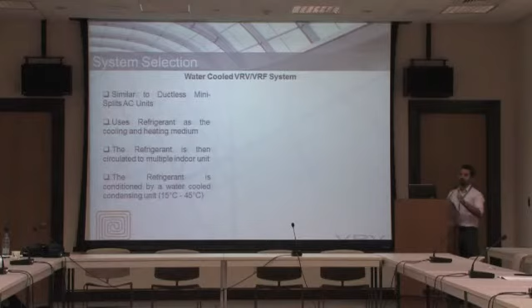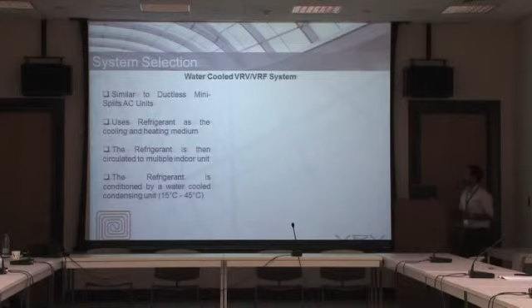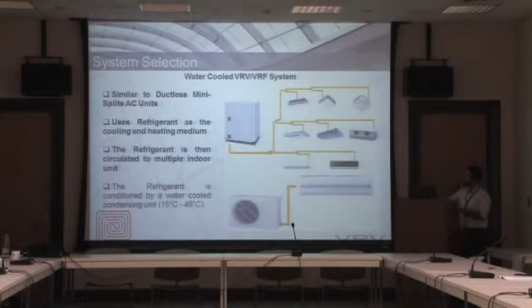Starting with the water-cooled VRV. Honestly, I didn't know what the water-cooled VRV was before I started this project. We usually work with an air-cooled VRV. VRV or VRF stands for variable refrigerant volume or variable refrigerant flow. It's similar to a mini-split unit. However, the VRV unit is connected to multiple indoor units, and it uses refrigerant as both cooling and heating medium. The tenant can control the amount of refrigerant flow at the evaporator.